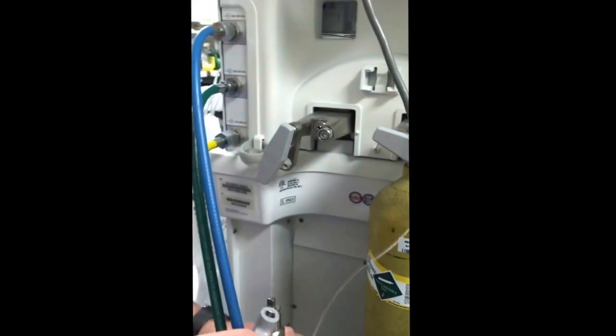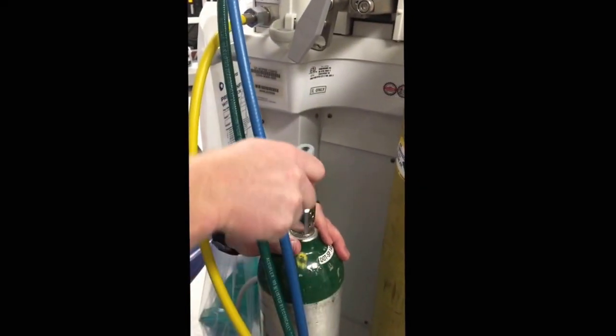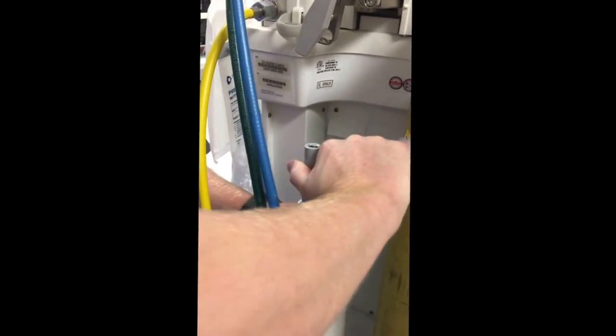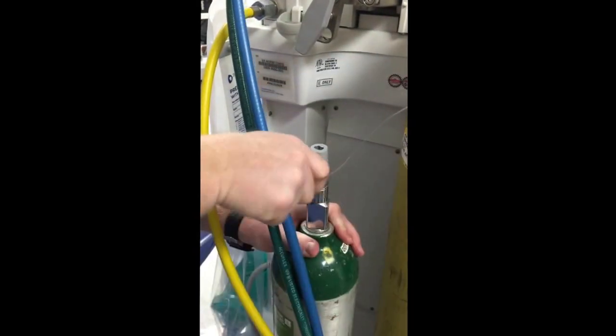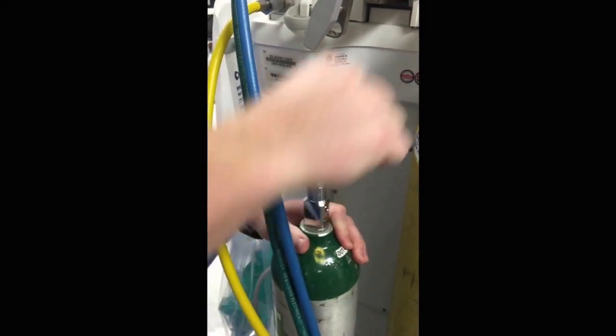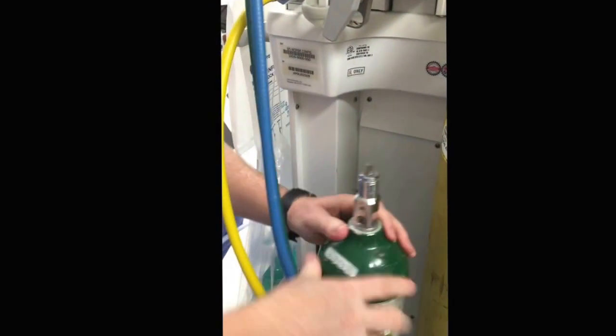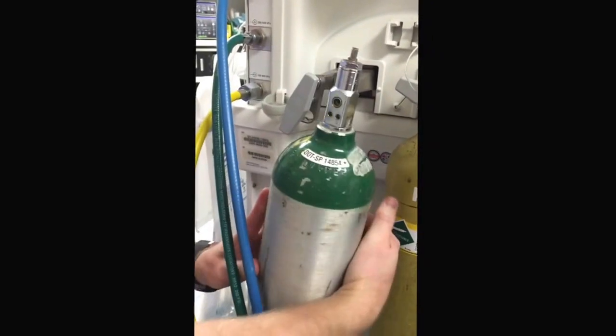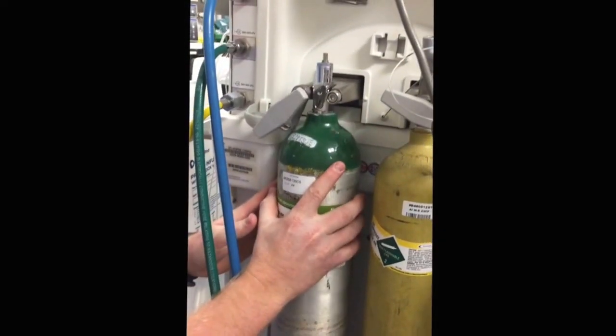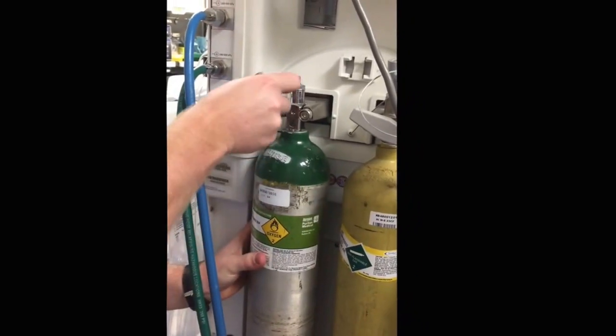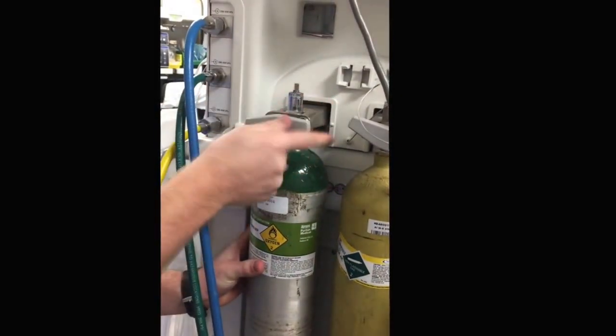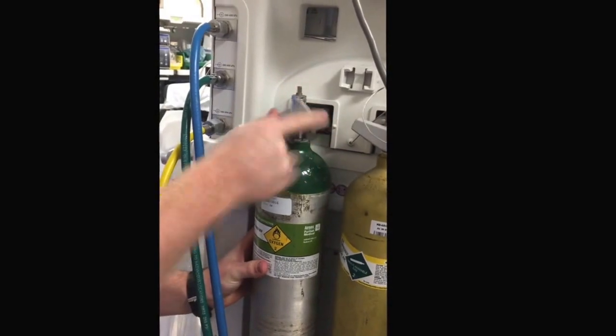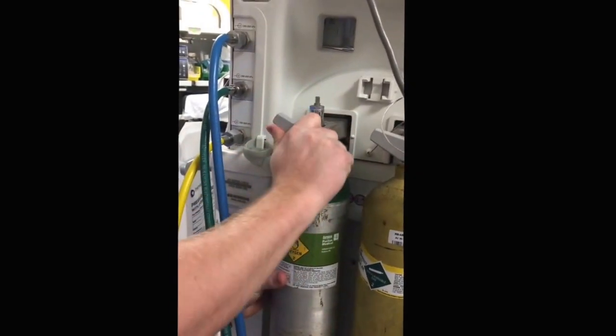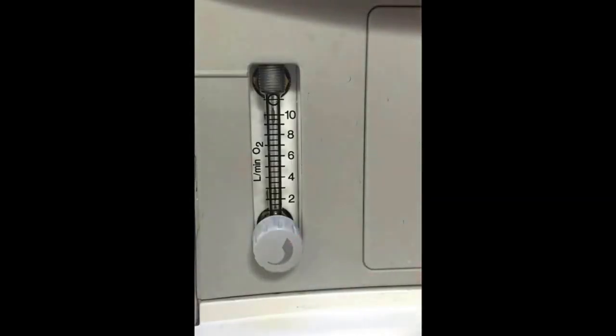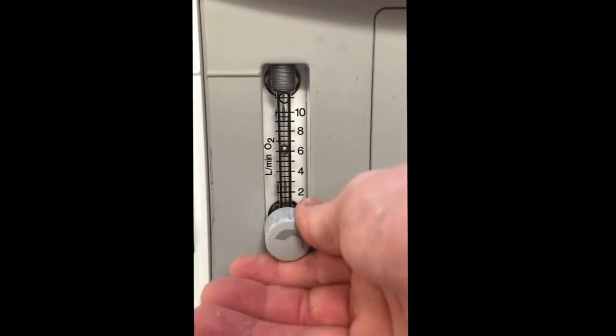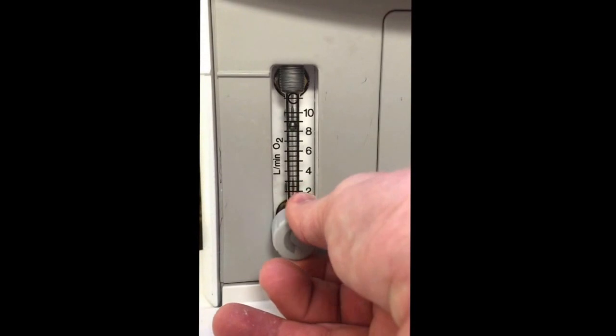When you come back with your new cylinder, you will open it before, to get any dust off of the cylinder. Once again, pin index safety, it only fits that specific cylinder. Close it and give this a good tightening. The last thing you can do is check your O2 auxiliary to make sure it is functioning.